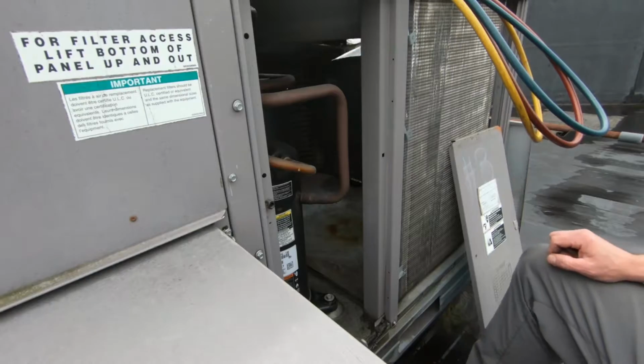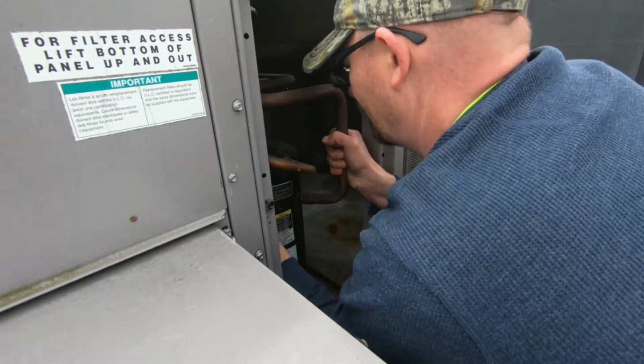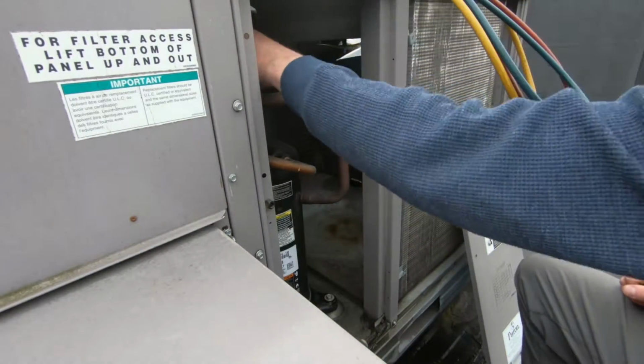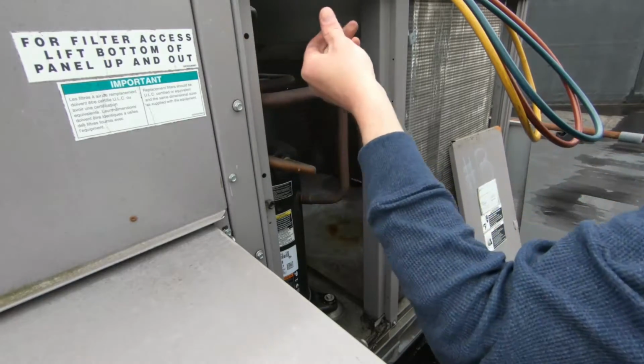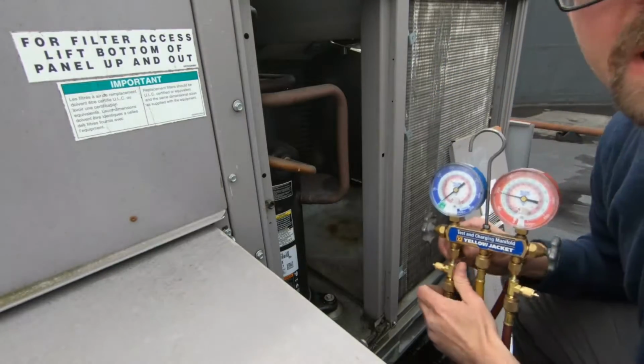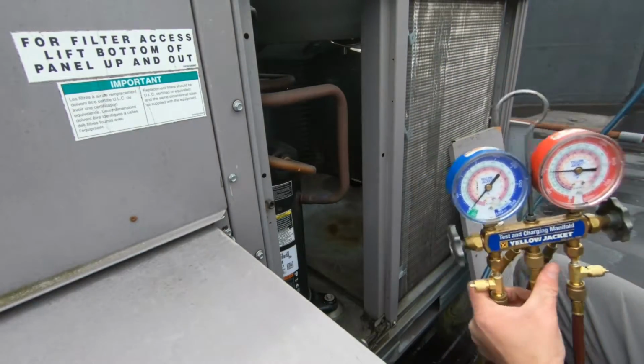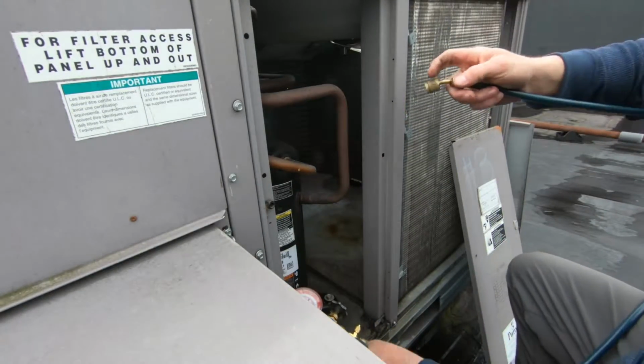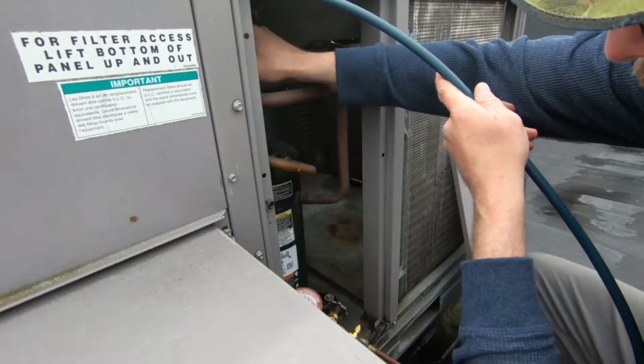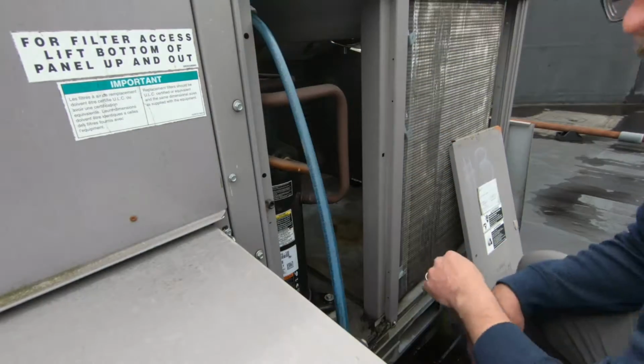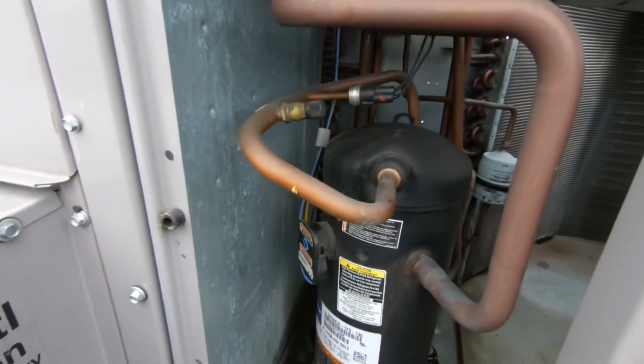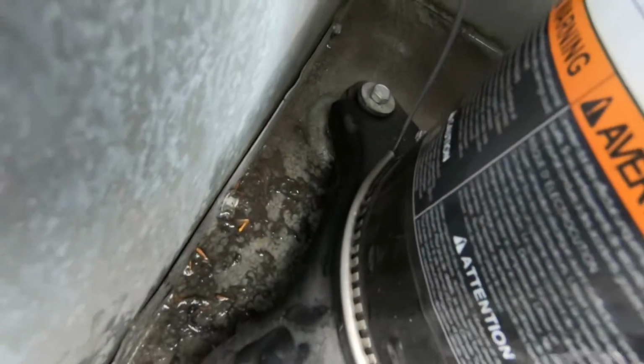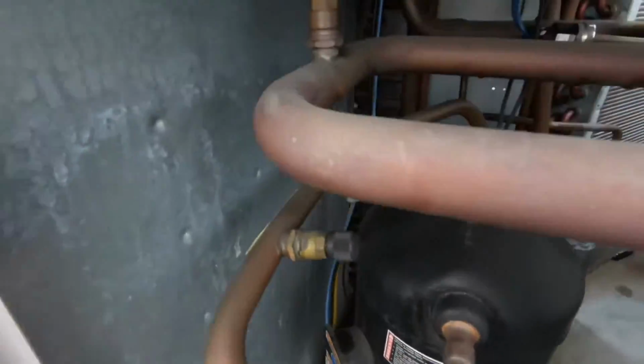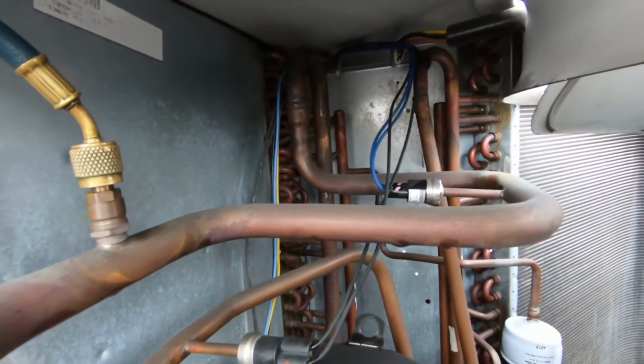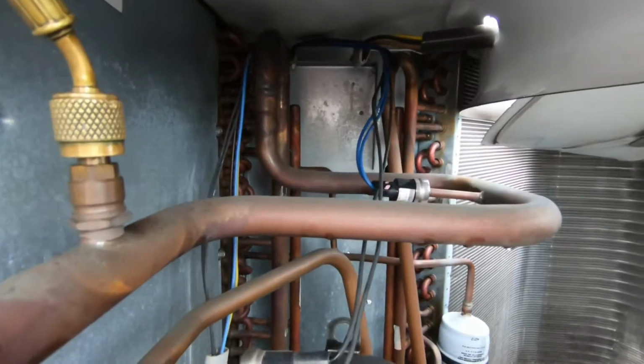A lot of grease coming out of the bottom of that condenser fan motor. All right. Let's see if she's holding some refrigerant. I don't like turning breakers on until I look at them and see why somebody might have turned that breaker off. Of course, they're doing a lot of construction and remodel here. Yeah, we've got pressure. I don't see any burn marks on the crankcase heater. We'll kick her back on, see what's up. I'm gonna test everything in the electrical panel, make sure that we don't have any direct shorts.